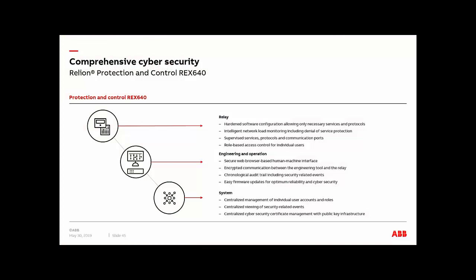Cybersecurity. In this part, well, the 640 relay was hardened with software configuration, allowing only necessary services and processes. It's got an intelligent network load monitoring, including denial of service protection, supervised services, protocol, and communication ports all the time. You also are going to get role-based access for individual users, where you can have different levels of access, and also the relay will give you a log of each of the accesses and people that logged into it to do any change. Everything will be logged on the relay in the sequence of events.